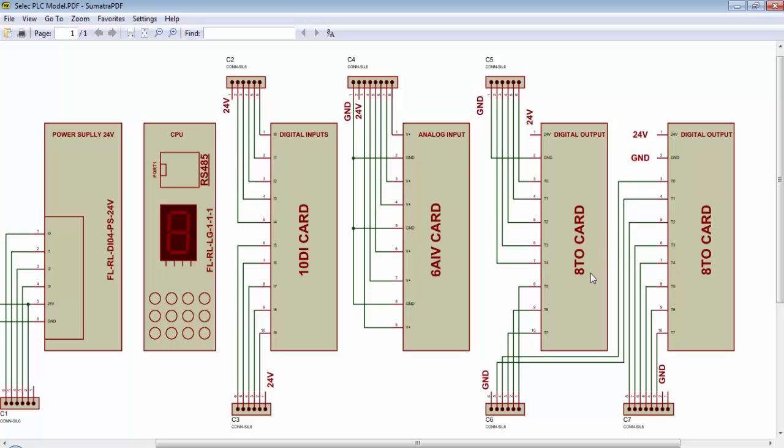So in this arrangement, we have 14 digital inputs, 10 from this 10DI card and 4 from this power supply card. We have 6 analog inputs of voltage type and we can measure the voltage from 0 to 10V. And finally, we have 16 transistor type outputs.